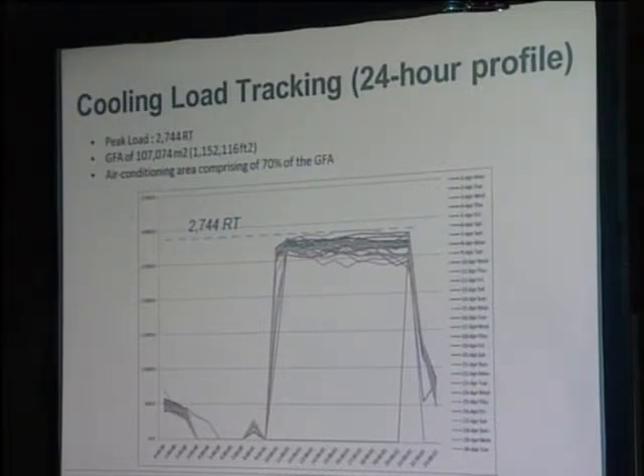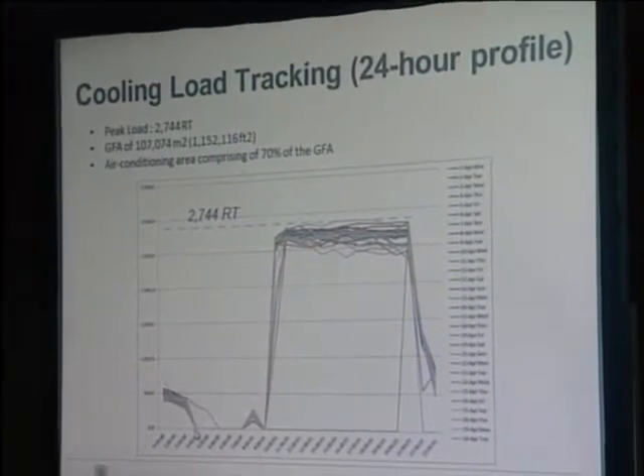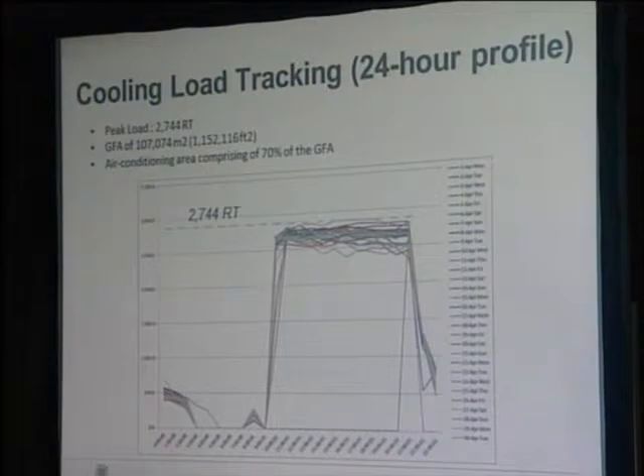Also, as part of the energy management, we looked at the cooling load over a 24-hour period. You can see around midnight it drops down at about 3 o'clock, everyone has gone home, there's some cinemas running, and then it starts up in the morning again about 9 o'clock. This is then the peak refrigeration tonnage, so the peak cooling rate was about 41 BTU per hour per square foot.